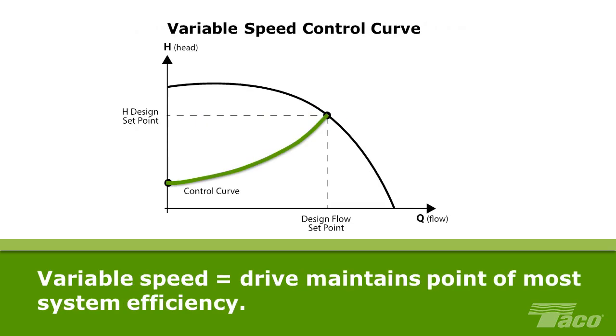It will maintain the same pressure regardless of system resistance. In a given variable flow and head application, the control curve represents the points of a theoretically most efficient system operation throughout the operating range of the pump based on the best placement of a differential pressure sensor as shown below. For more information, please see our video on control curves and setting self-sensing pump control modes.